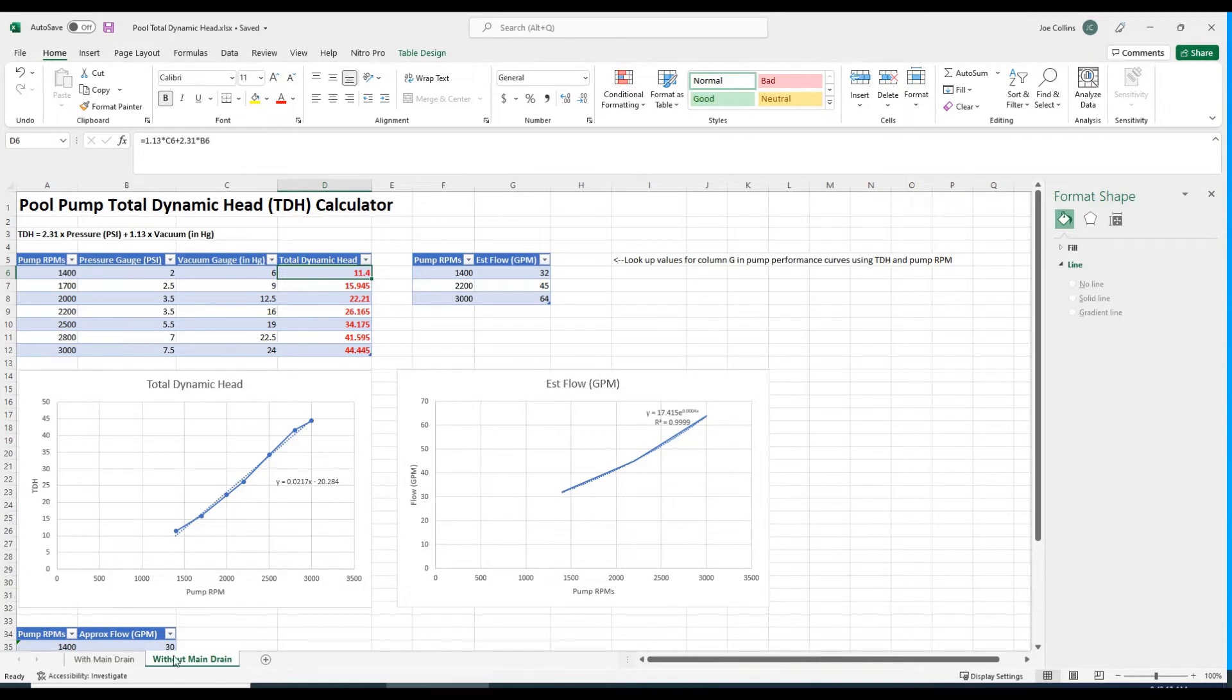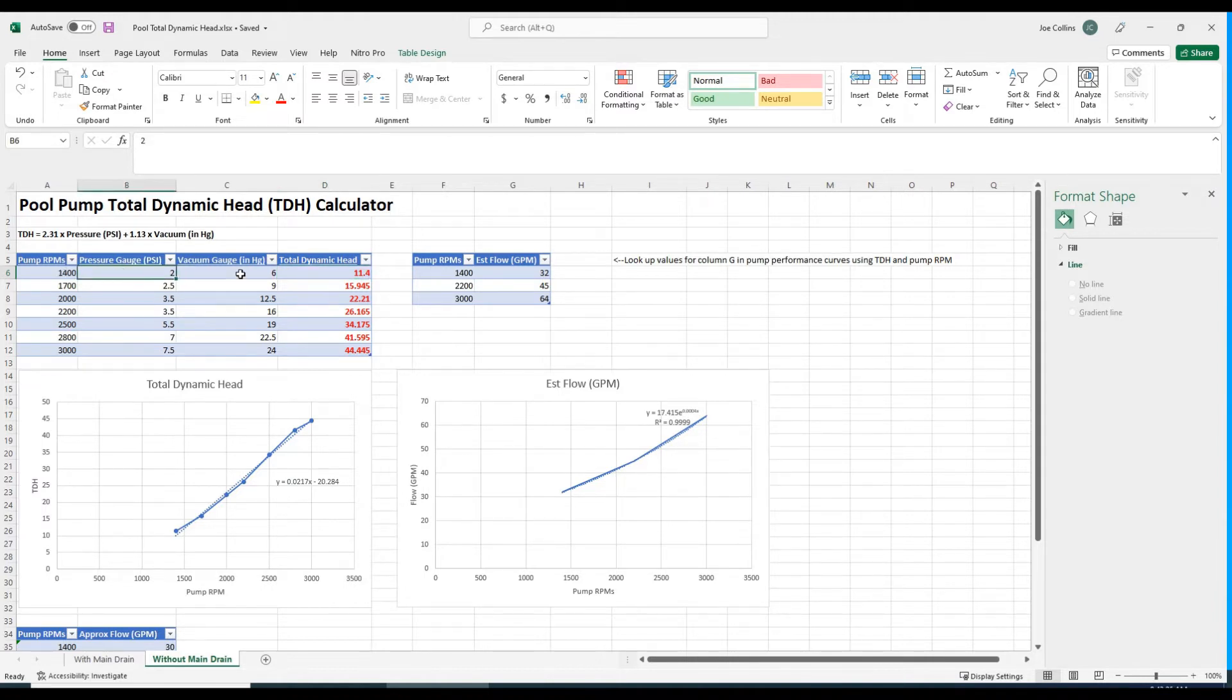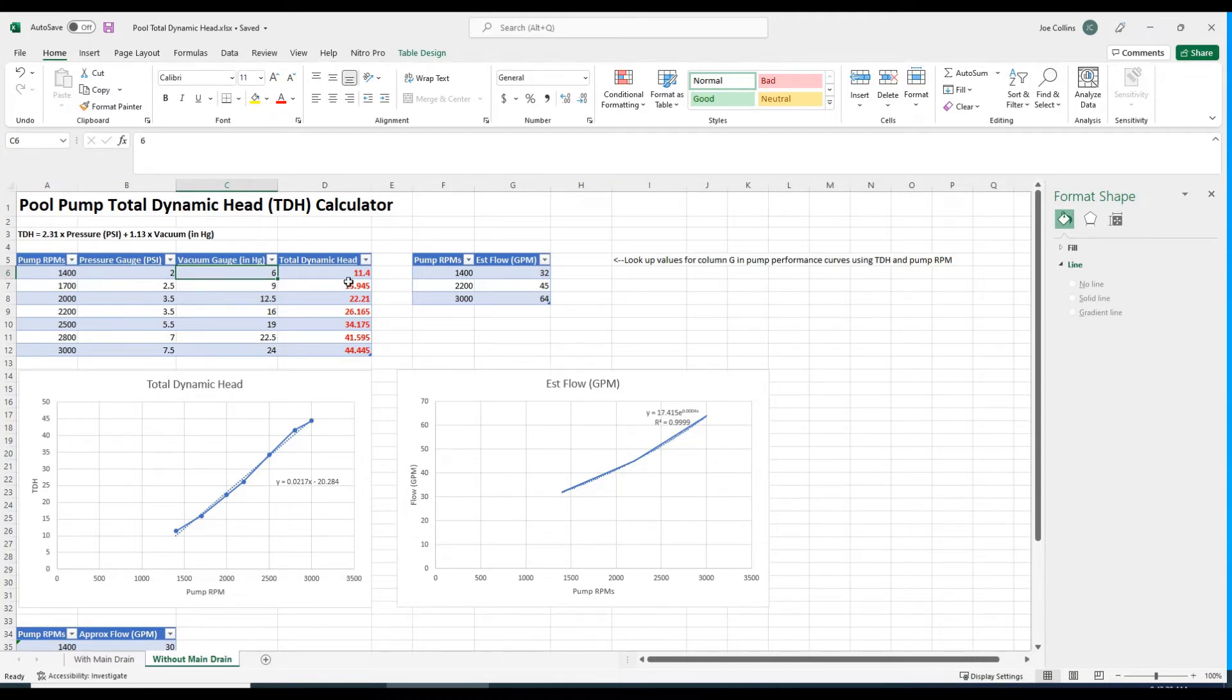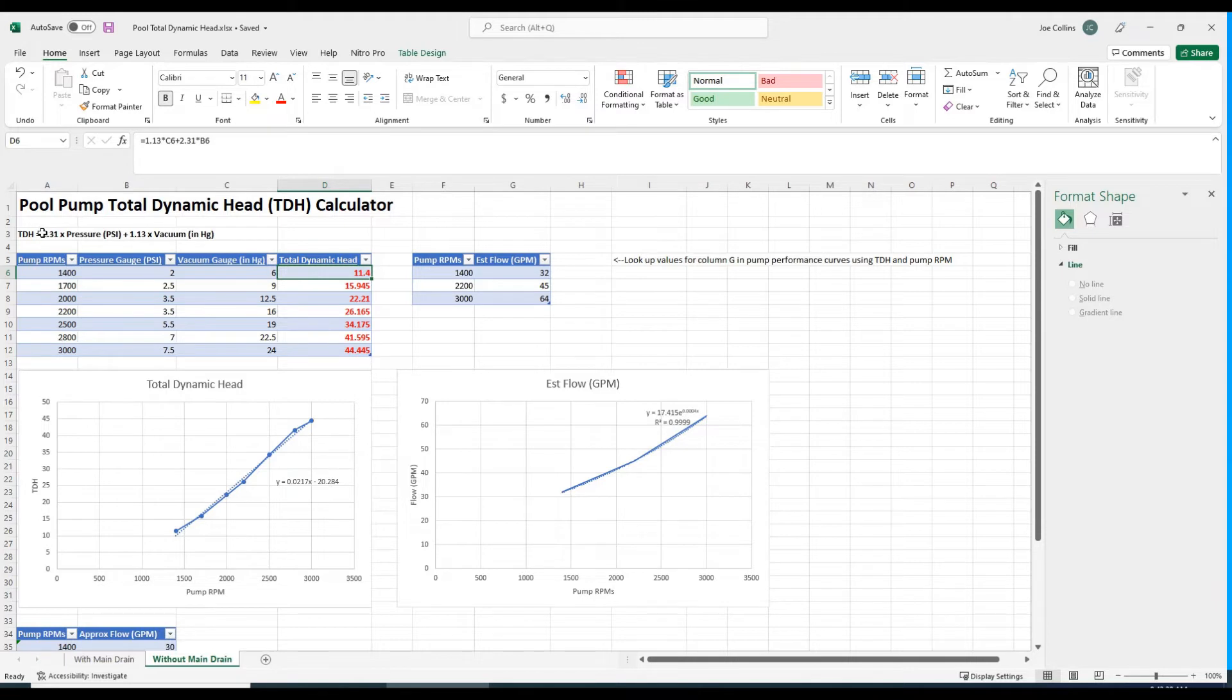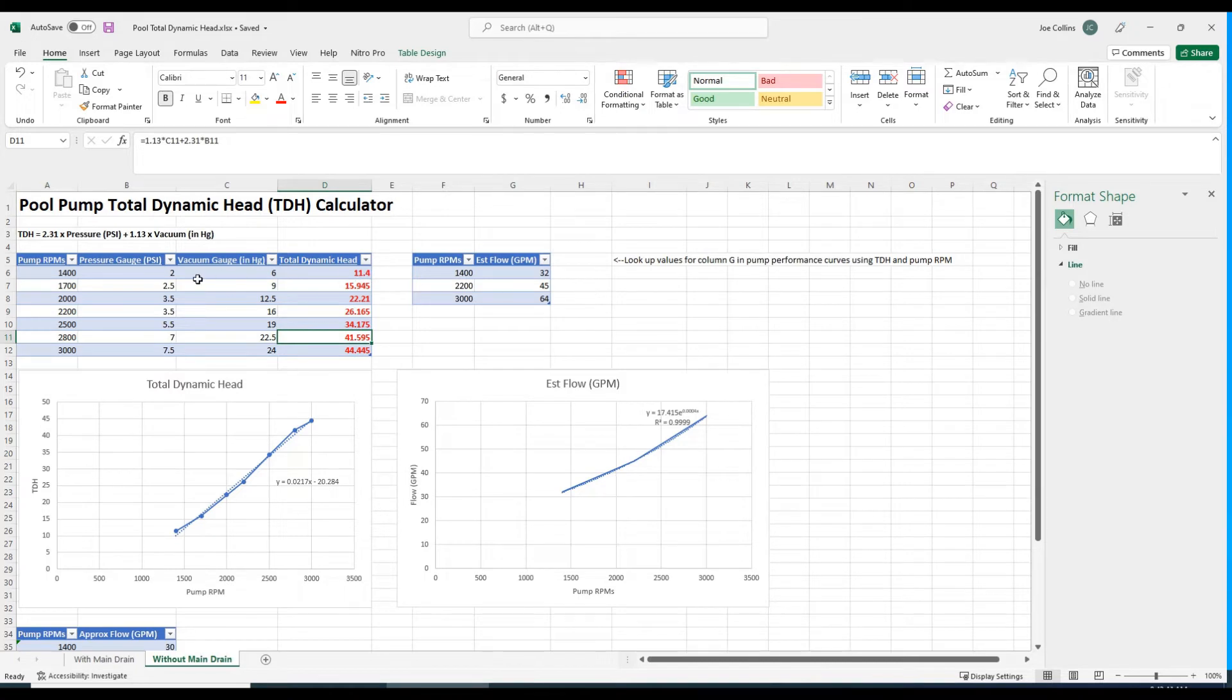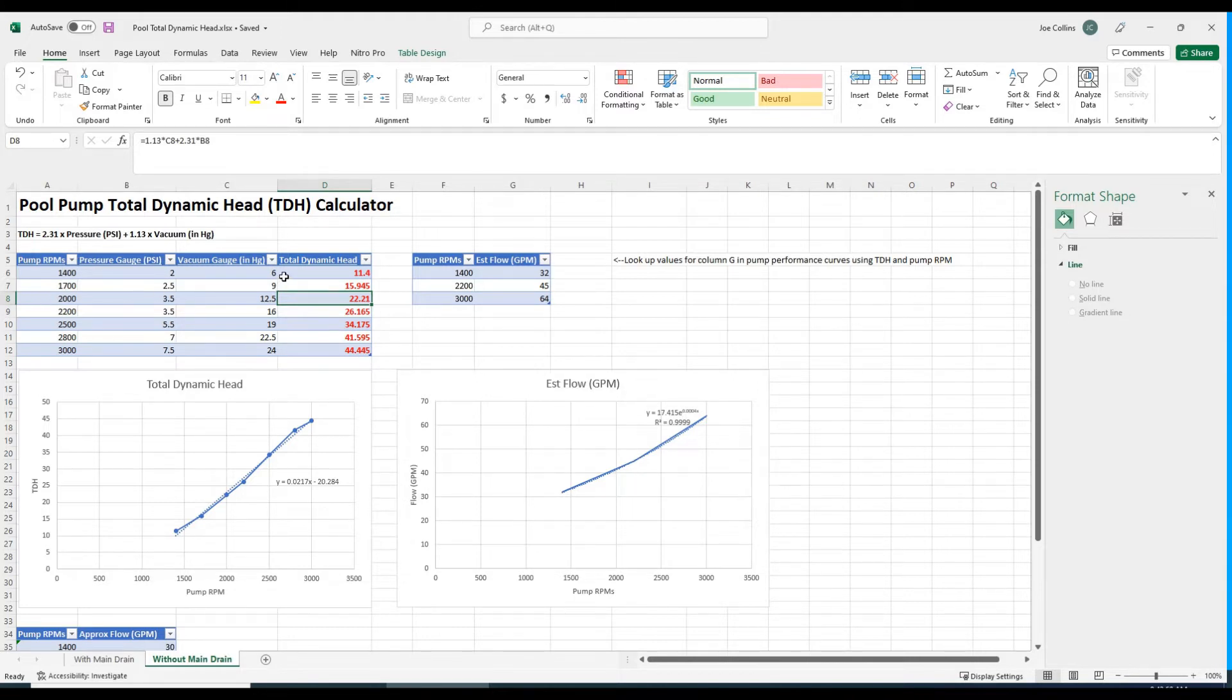Let me walk you through one of these tabs. We measured the pressure and the vacuum at various RPMs. Those pieces of information, the pressure and the vacuum, can be used to calculate total dynamic head. That's done by this formula, which is pretty straightforward. Excel does all the heavy lifting.